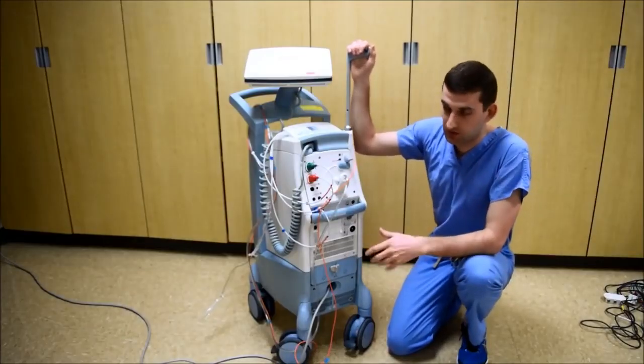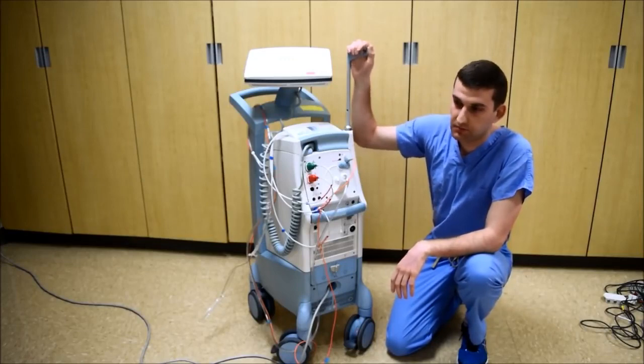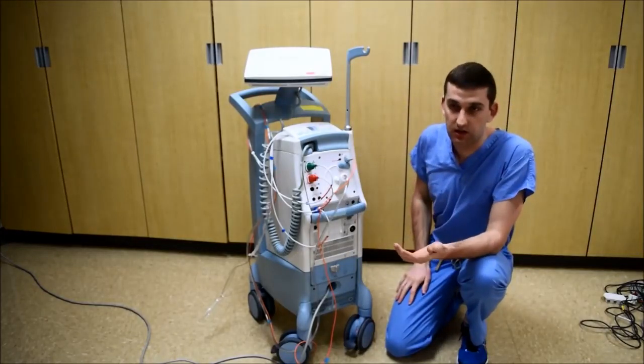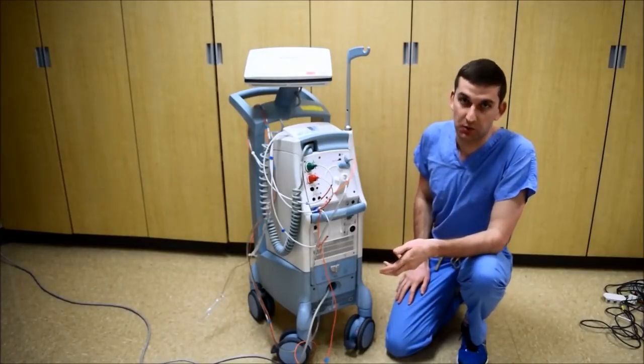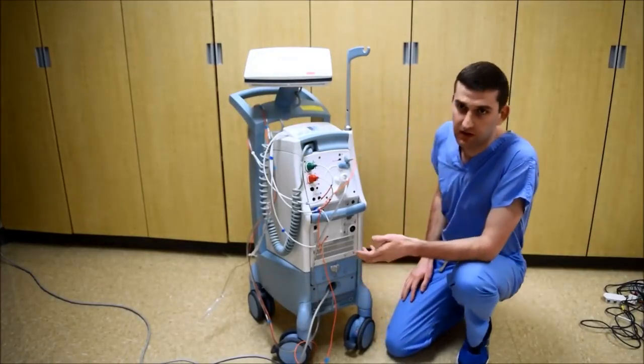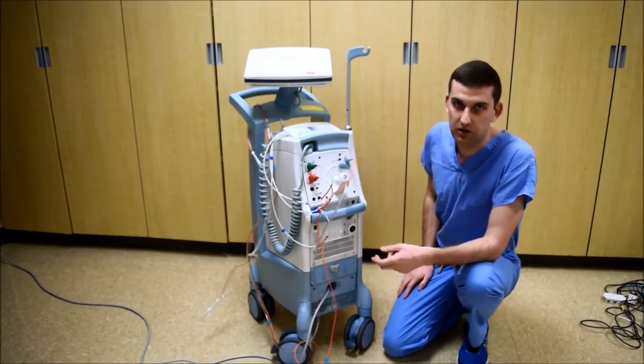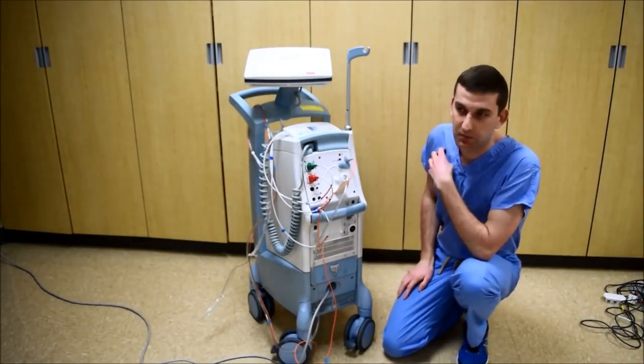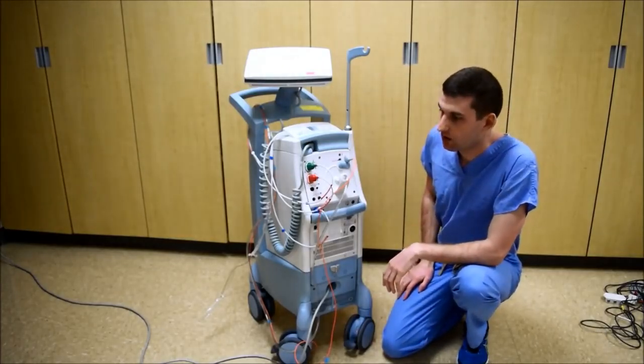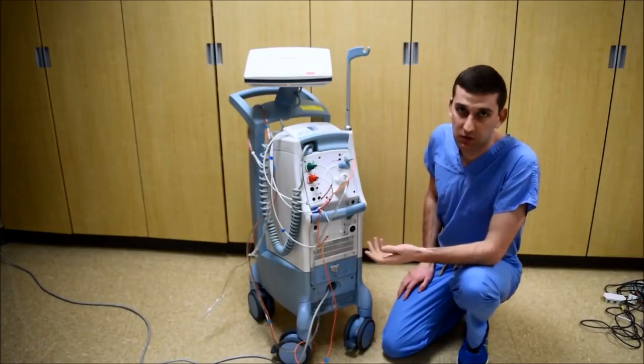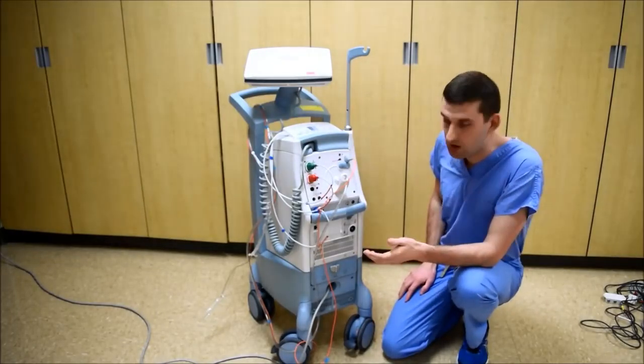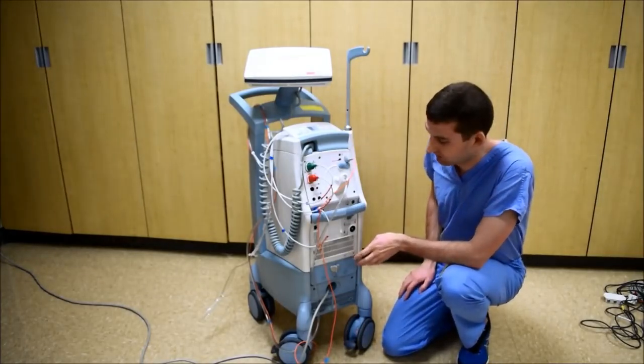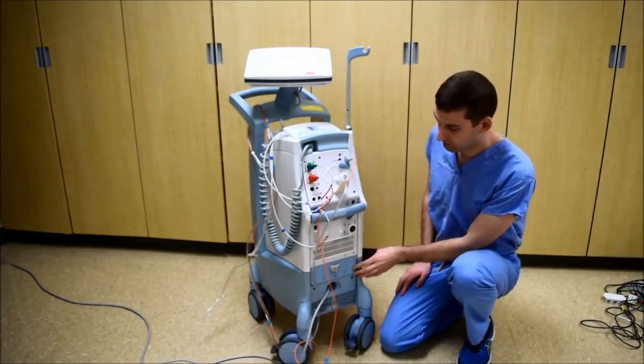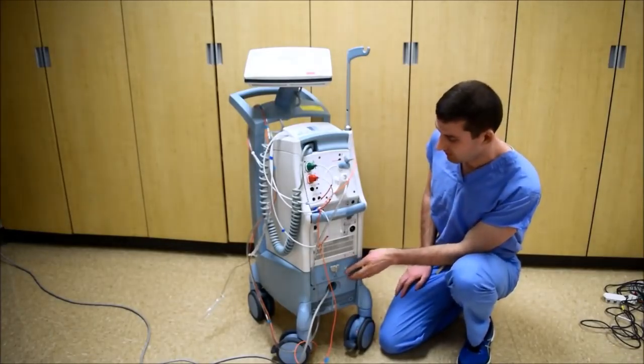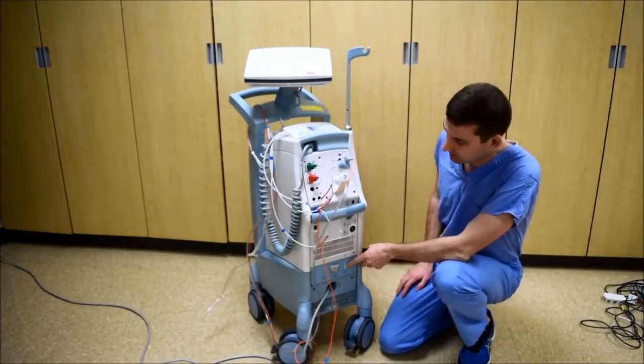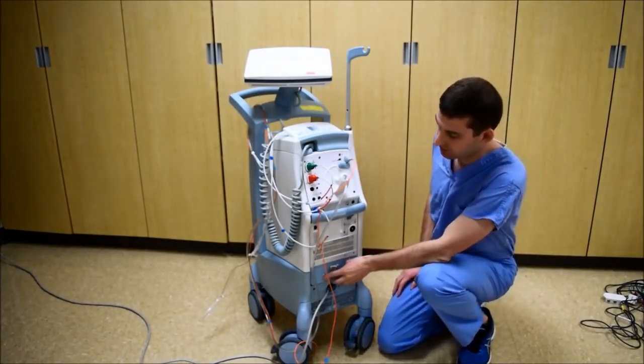If you're planning on traveling with the balloon pump, there's a few things you should consider first. One, you want to make sure that your destination is aware of your arrival and has all the appropriate equipment in place. Secondly, you may want to consider giving the patient new ECG leads and taping them on so they're snug. You're also going to want to make sure that you have all the appropriate equipment for your travels. Having an extra set of batteries is also a good idea. The batteries are located down here. You can see their level of charge by the LED lights that light up above here after you press this button.